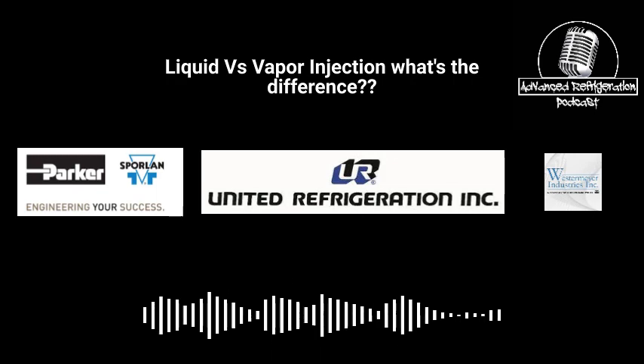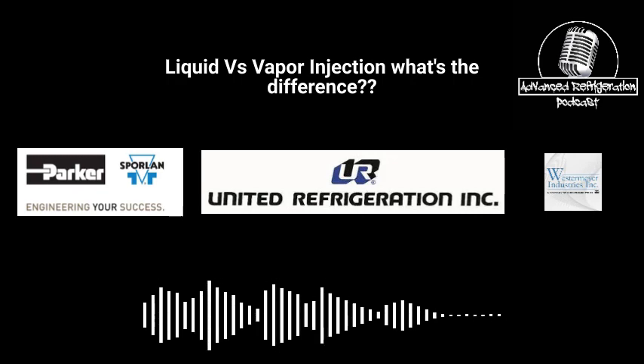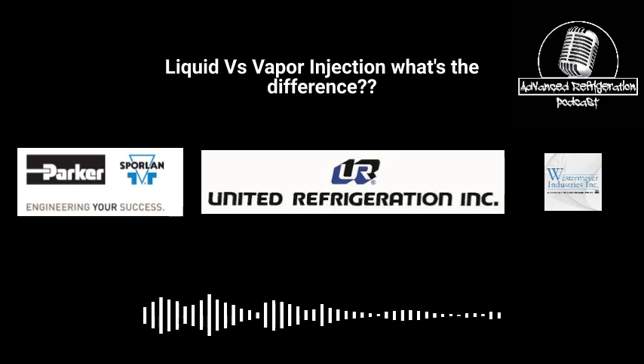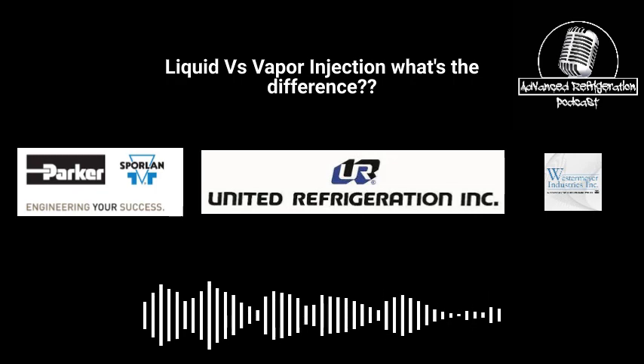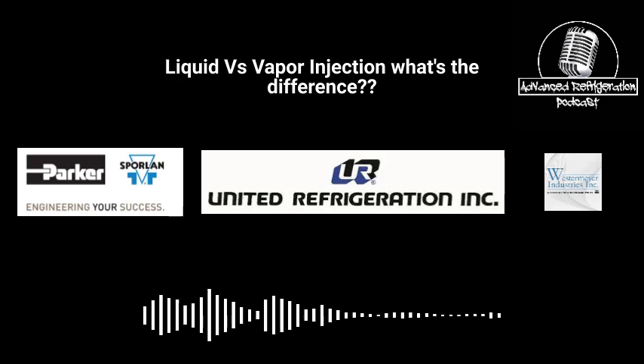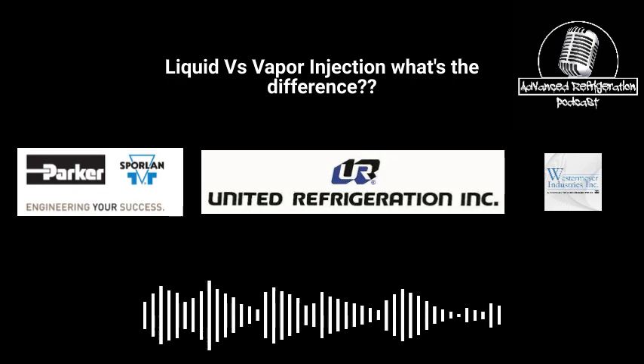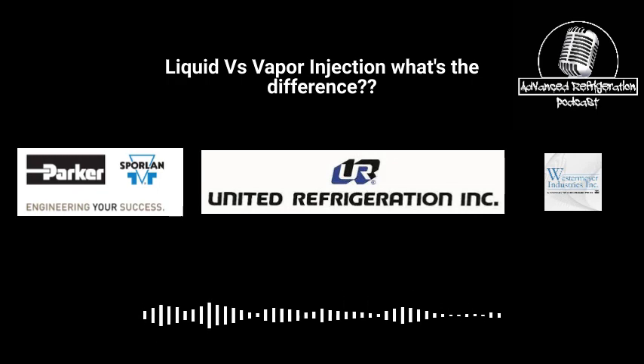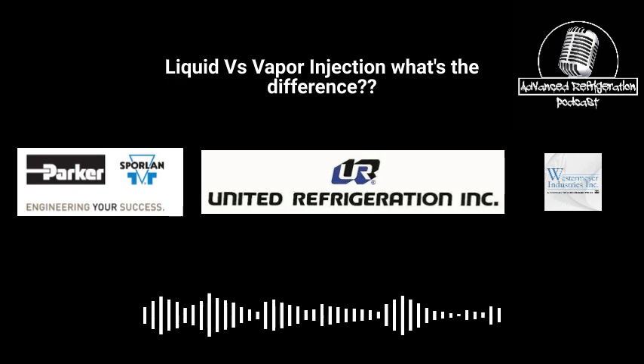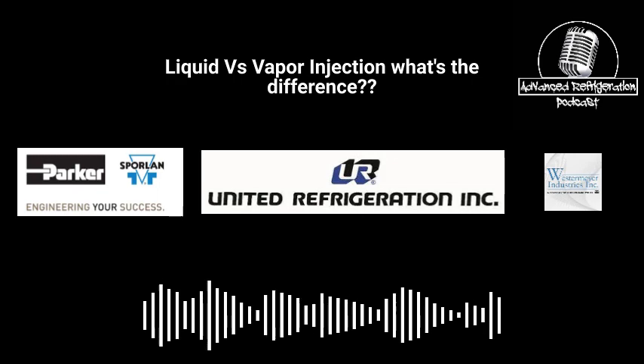And I know we've talked about this before, when setting up EPRs, you want to use midpoint. When setting up your rack suction, you want to use midpoint. If you're just trying to measure superheat, just go off of what the dew point is. But that's a surefire way to make sure that you're not going to run too far down where that liquid line solenoid is going to shut that off, because a rack likes running steady, right? We don't want to keep shutting things off and on, off and on. So it's recommended to make sure that the subcooler solenoid is running all the time. We don't want it satisfying. We want to keep cool vapor entering those compressors all the time.